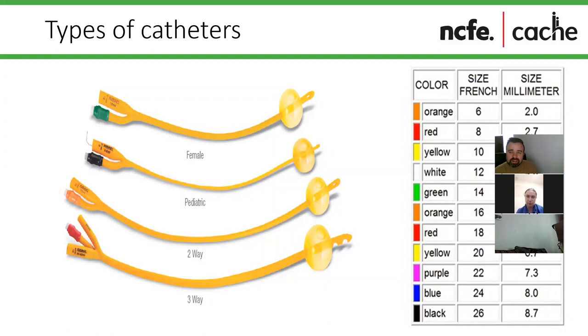So you can see here, you've got different sizes. So you've got female, male, 2-way and 3-way. So they'll be prescribed for you. That'll give you an idea. And you can see on here, if we look at the top one, for example, you've got your green bit, that's for filling the balloon up. So once they're inserted, we fill that up with normally 10 mils of water. And that would pop it into place nice and tight. And if we wanted to flush the catheter or we wanted to put the bag on, then we use the opposite tube. So we use the big rubber tube for flushing, and then we use that one for filling the balloon up. So very much like that peg button, it's done in a similar way.